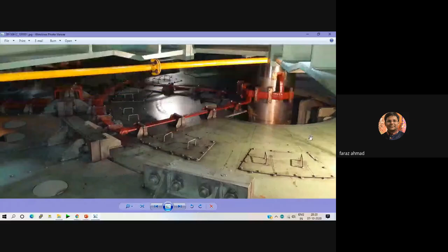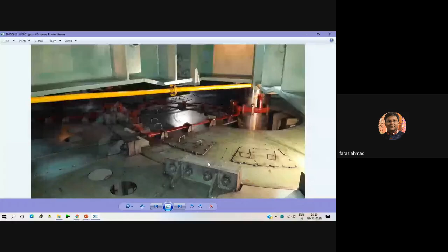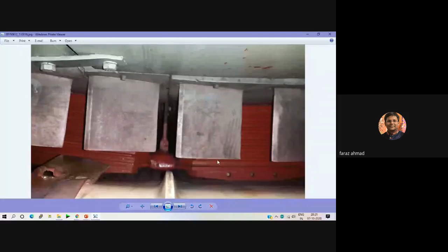This is this metallic structure. This is the rotor. This was taken while I was standing on the rotor. So just imagine the size of the machine. So this is the rotor. Red, these are the conductors coming out from the carbon brush collector, carbon brushes, which is installed somewhere over here. So what happens is that there are slip rings and brushes that transfer the excitation current into the system. So those are placed over here, somewhere here. It comes down and forms a complete circuit. So this circuit is for excitation, the field windings.